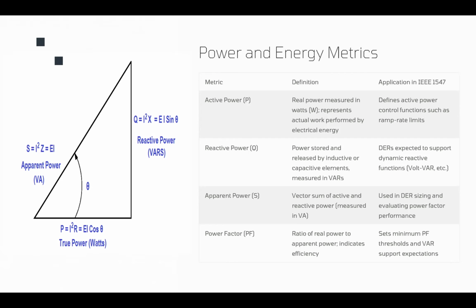A power factor, as you can see in the slide, is a ratio of real power to apparent power. So if we know the apparent power and we know the active power, now we can control the power factor. Now we can measure the power factor. We can adjust the power factor. So it also can be used sometimes for the reactive power control, because sometimes instead of directly defining the reactive power amplitude, we define the reactive power as a percentage of the apparent power.